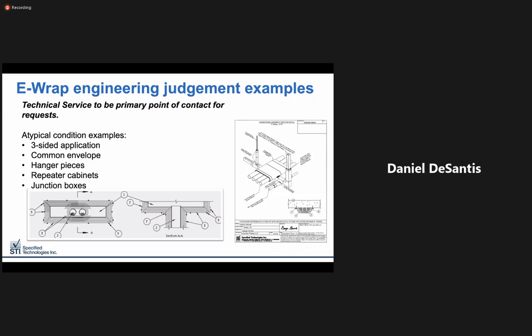Below that is a section view of 3 conduits run tight against the concrete floor. This is a low-profile design that is popular in the retrofit market due to its space efficiency. These conduits are protected with what's known as the clamshell method. Layers are half-mooned and mechanically fastened to the deck instead of wrapped around the full circumference. This is great for cast-in-place walls and floors, since shorter standoffs can be used to protect finished ceiling height.